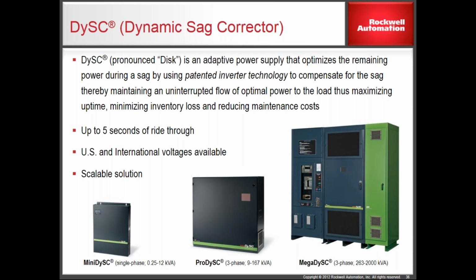Now the phases swap. In that first 1/10 of a second, all this ugly voltage signature comes rushing down the line at your plant. The DySC turns on, protects you from all that. Finally, it runs out of energy, hands it back to the line. Well, by this point, the breakers have all popped, the line is dead. So you get a clean drop to 0 instead of some awful drop. So your equipment's protected from damage due to an outage, and it rides you through all the sags.